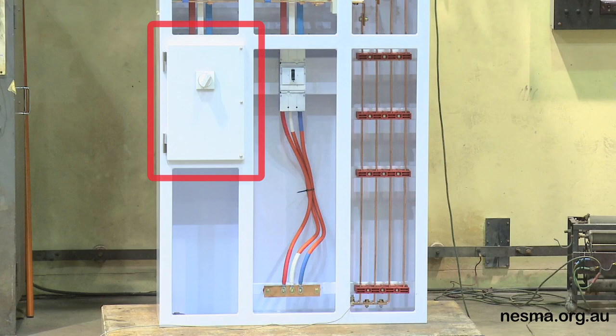Thanks, Alan. It was very interesting. Okay, the grand finale. So the test number 4, Max mentioned as an unlimited arcing test, which will start on the line side of the breaker. Our objective is to show pressurisation of a functional unit with arcing from a line zone fault. The result will hopefully be more extreme, much more violent than tests 2 and 3.